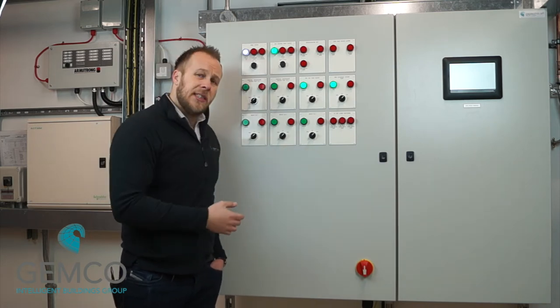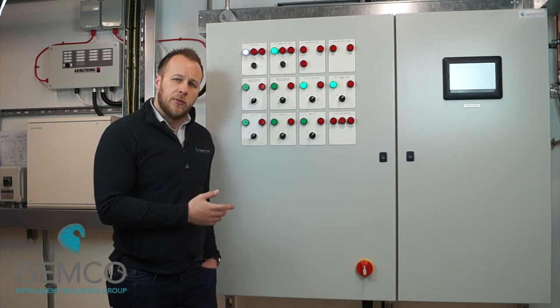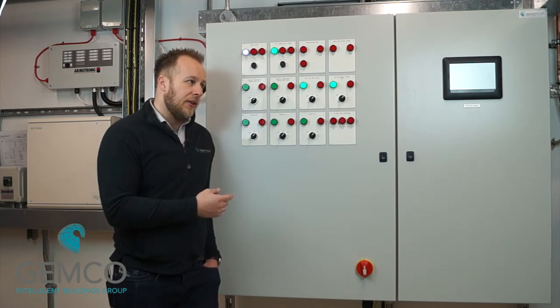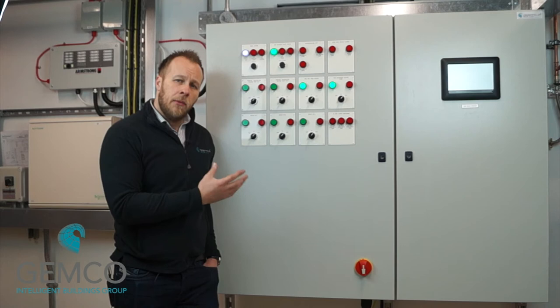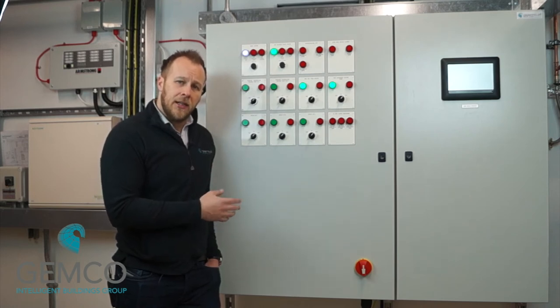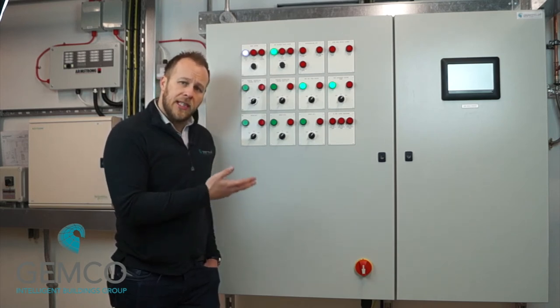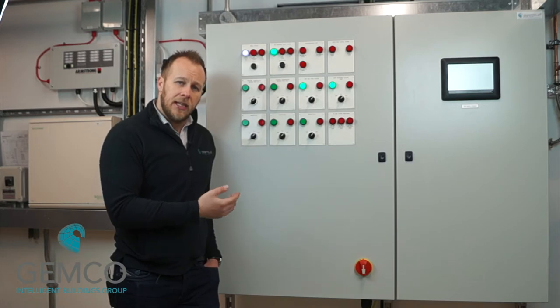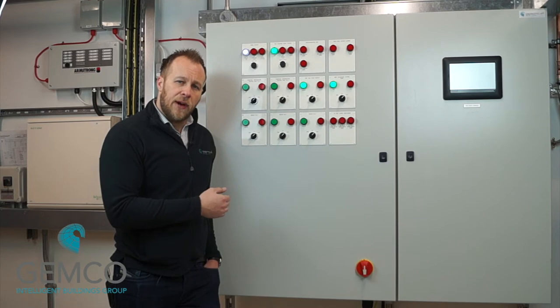Okay, and then the last stage of frost protection is fabric frost. We've got numerous temperature sensors located in the space, and we'll monitor those, and if it drops below 16, we'll bring on the pumps and the boilers just to elevate the temperature in the space, because we don't want to damage things like plaster, paint, and all the fabric in there.